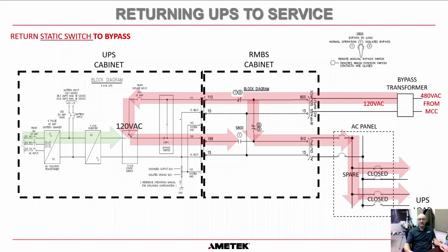And then what we need to do is return the static switch to the bypass position, because we are getting ready now to move to position 1. When we move to position 1, we are going to make this contact, and then we are going to break this contact. So we need to make sure that both sides of this switch are the same voltage and power. So we have bypass here, and we have bypass on this side here. They are identical. You can't go wrong. Okay.